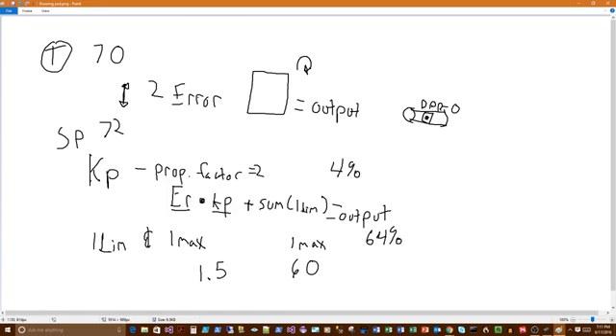And when you're tuning things, you also have one more value, which I'm going to put over here, and that's called your STUP value, or startup. And so you could say that I want it to start up at 25. That means your output is going to start off at 25%. It's always going to get 25% at least. And so when you're tuning your PID loops, you'll want to figure out what your STUP value is. You'll want to know how fast your loop reacts, and that will determine your ILim right here.